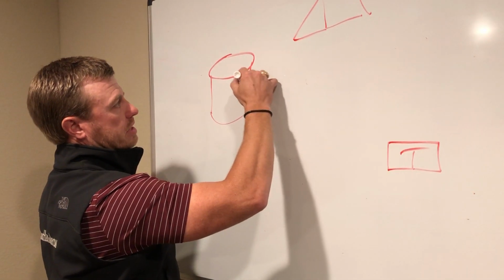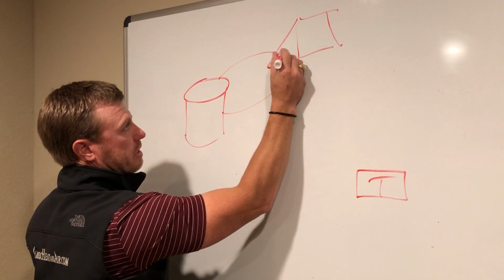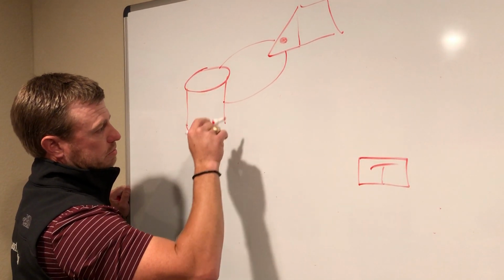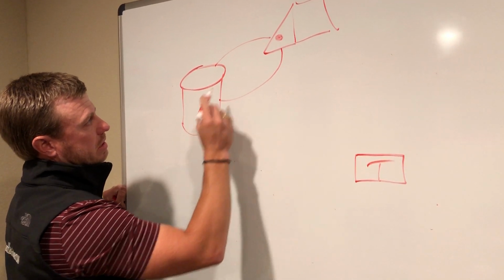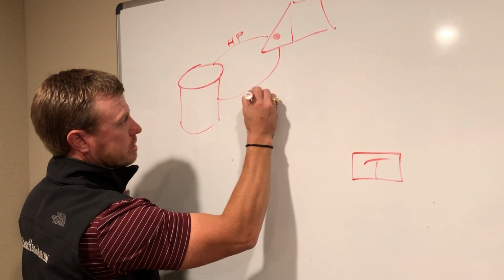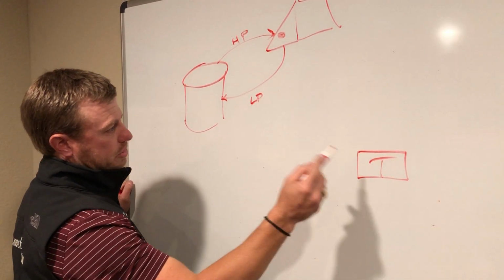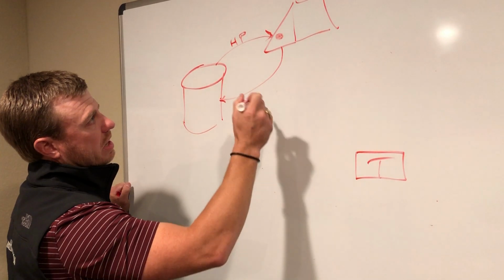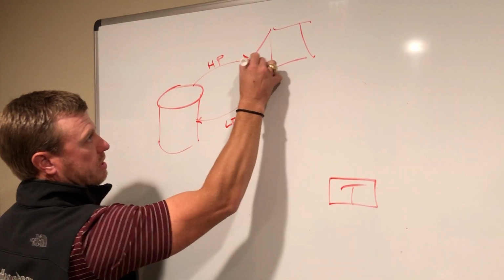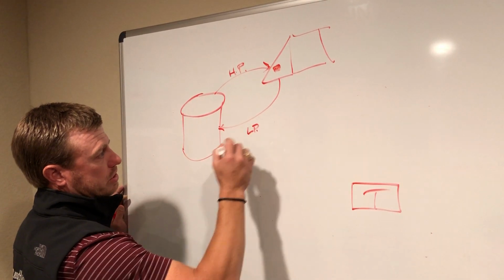These units, both the condenser and the evaporator coil, are moving a refrigerant between the two, and they're going to go through an orifice or an expansion valve of some type to meter the refrigerant flow. Whenever the condensing unit's running, you will have high pressure going to the coil, low pressure returning back to the condensing unit to be compressed again. When the thermostat's energizing this cycle and getting it running, and then the unit turns off, immediately this metering device will divide the system essentially into high pressure and low pressure.